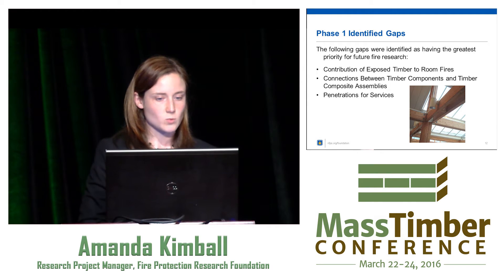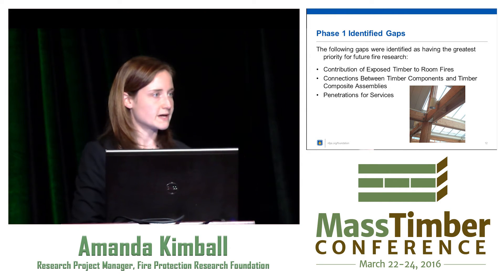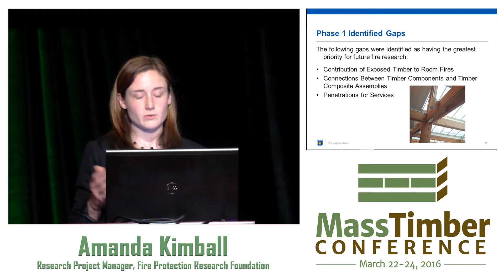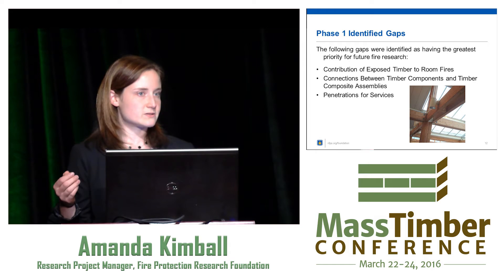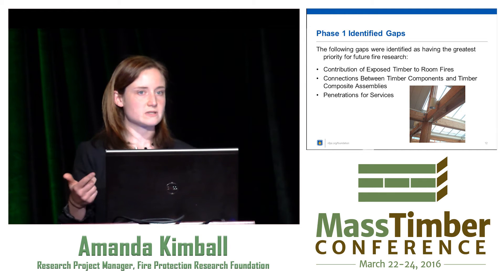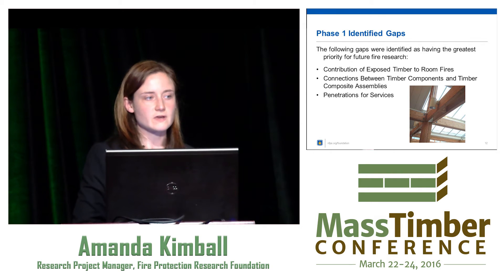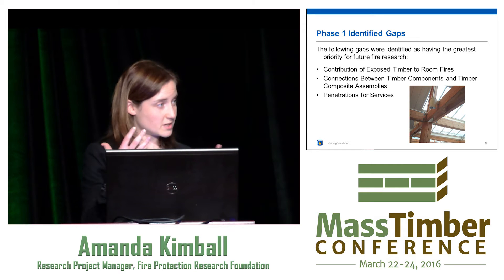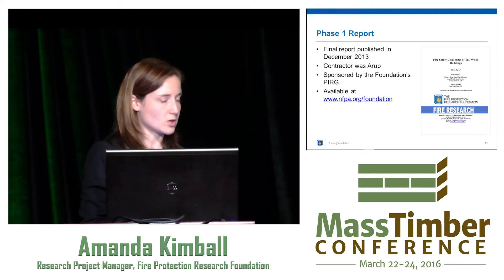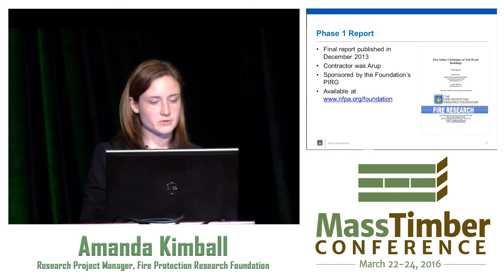The top three gaps identified from Phase One, having the greatest priority for future research, were: first, the contribution of exposed timber to room fires; second, connections between timber components and timber composite assemblies — there's a lot still not known about how timber connections behave in a fire and how that impacts structural performance; and third, penetrations for services — how do you fire-stop those in mass timber and how effective is that over time. The report was done by Arup and is available on our website, sponsored by the PIRG.